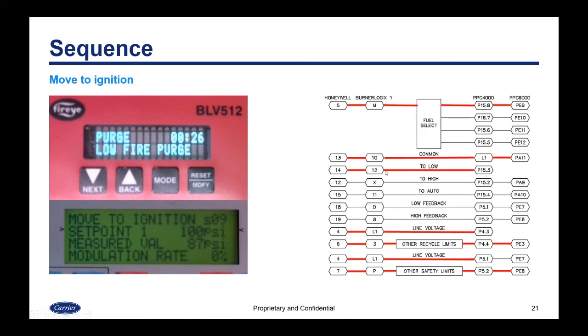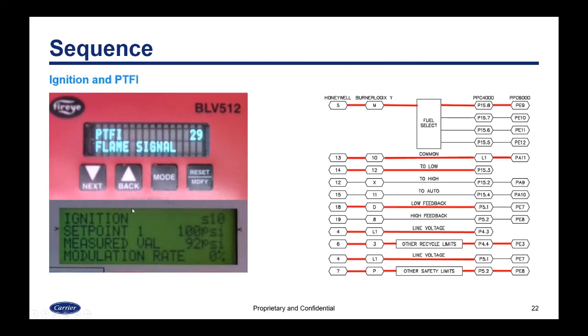At this point, the flame safeguard has changed the signal to tell it to drive to low. And there's no feedback right now, so it's moving to the ignition position. Once it gets to the ignition position, the only difference now is it has received feedback. The flame safeguard has received feedback from the PPC that it is at the low position. So it's still telling it to be at the low position, but now it's received feedback. That means it is at the ignition point. So the PPC displays ignition, and now the flame safeguard goes through ignition and PTFI.